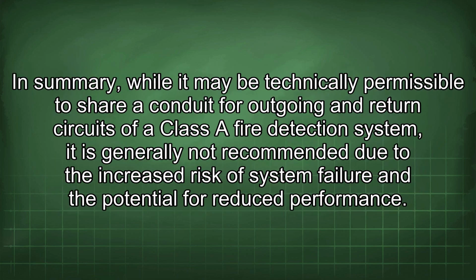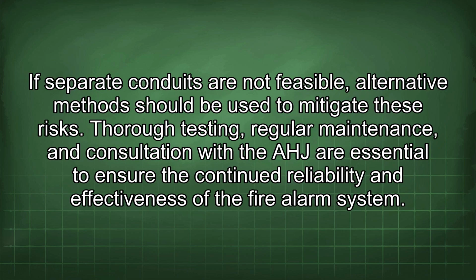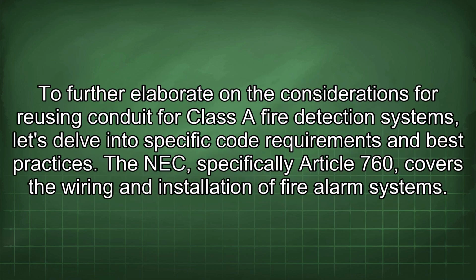In summary, while it may be technically permissible to share a conduit for outgoing and return circuits of a Class A fire detection system, it is generally not recommended due to the increased risk of system failure and the potential for reduced performance. If separate conduits are not feasible, alternative methods should be used to mitigate these risks. Thorough testing, regular maintenance, and consultation with the AHJ are essential to ensure the continued reliability and effectiveness of the fire alarm system. To further elaborate on the considerations for reusing conduit for Class A fire detection systems, let's delve into specific code requirements and best practices.